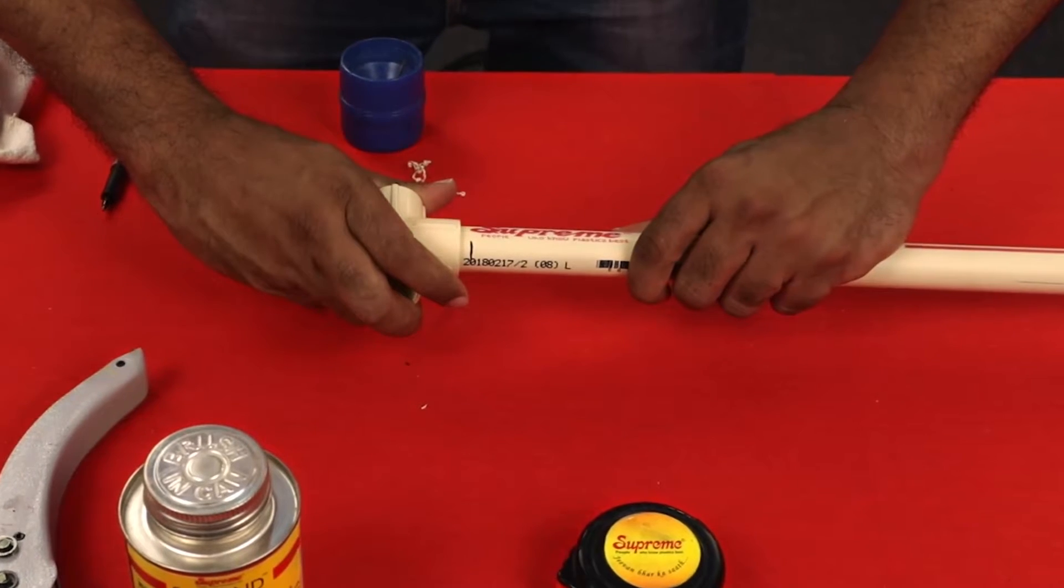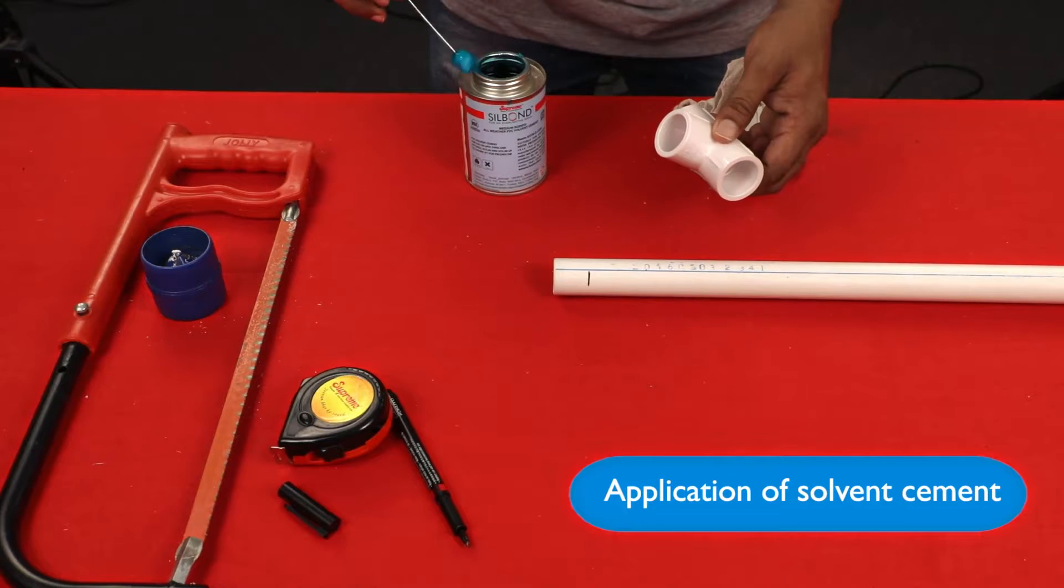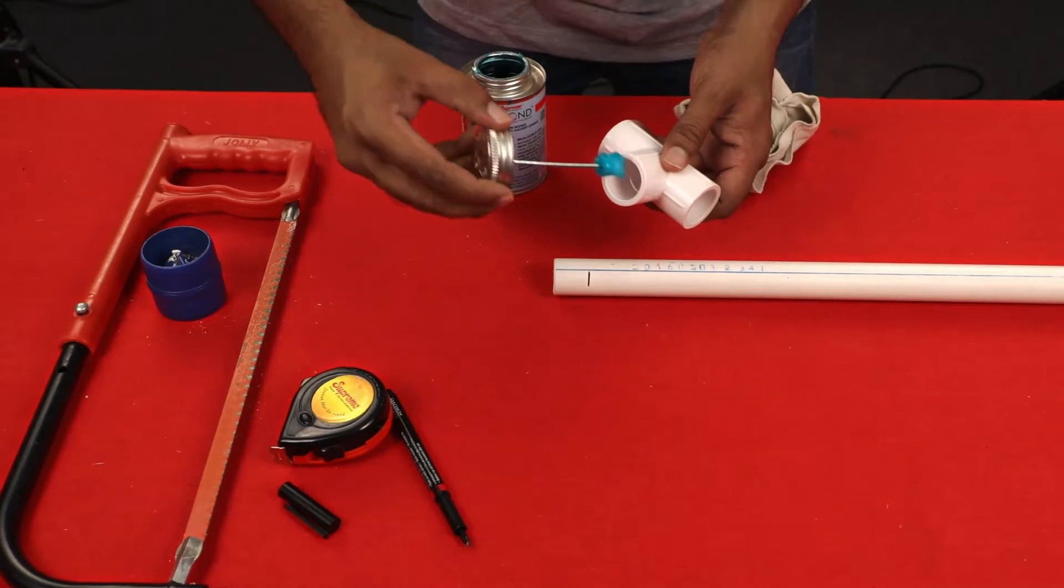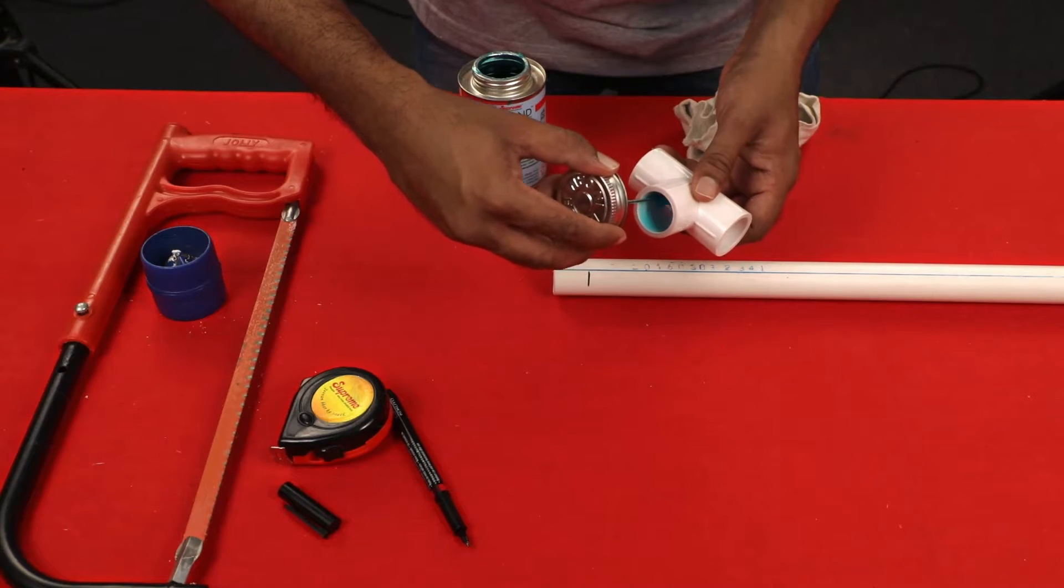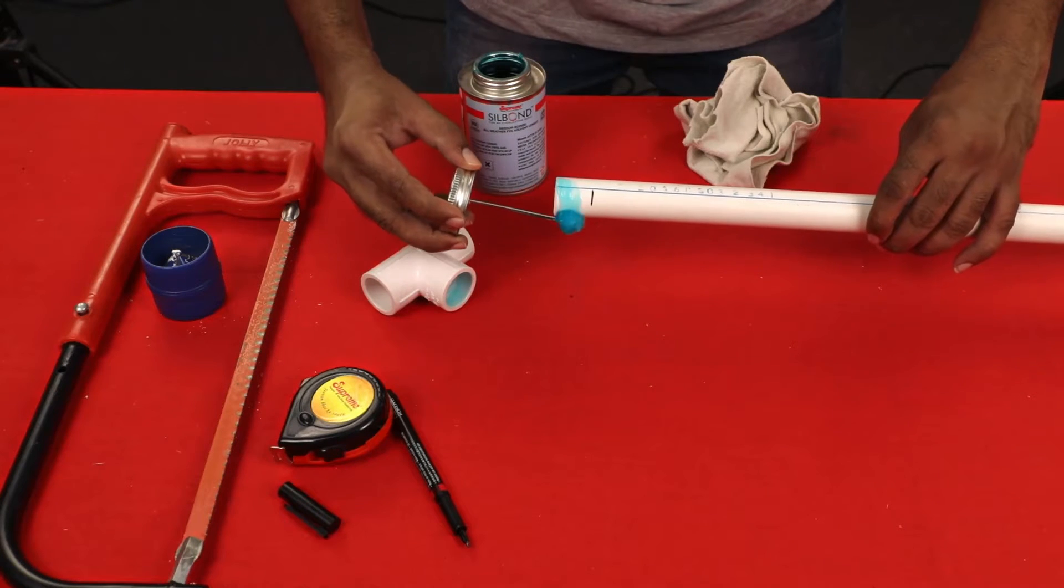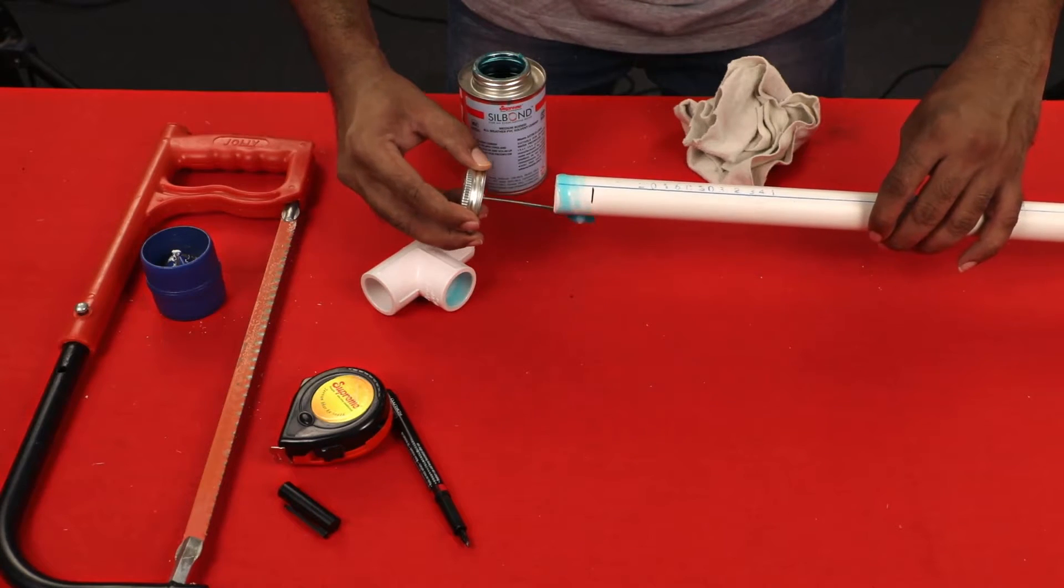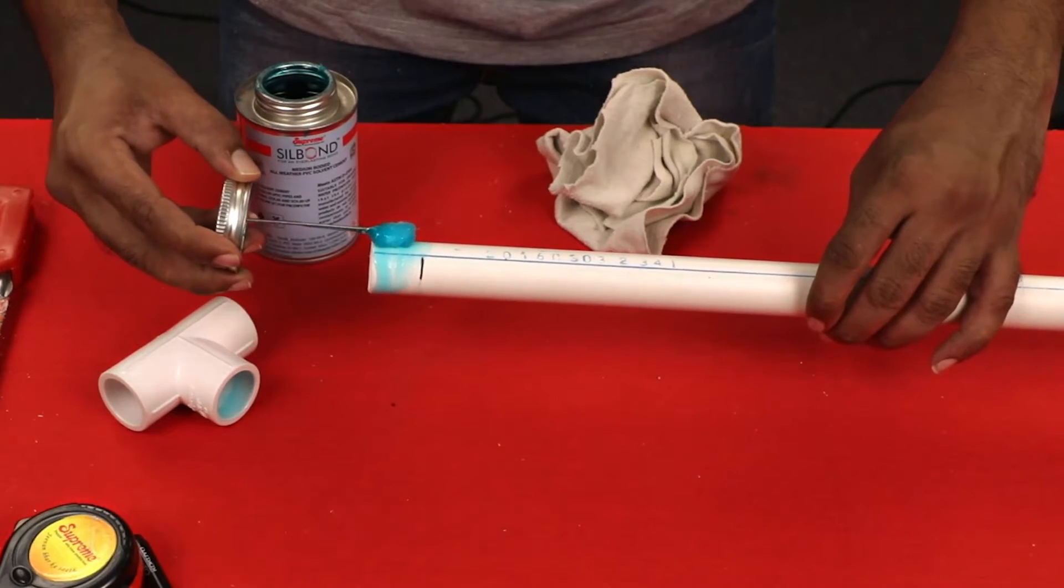Application of Solvent Cement: While making a joint, apply the solvent cement lightly but uniformly to the inner surface of the fitting socket and the outer surface of the pipe end using brush or suitable applicator. Apply a second coat of cement to the pipe end.